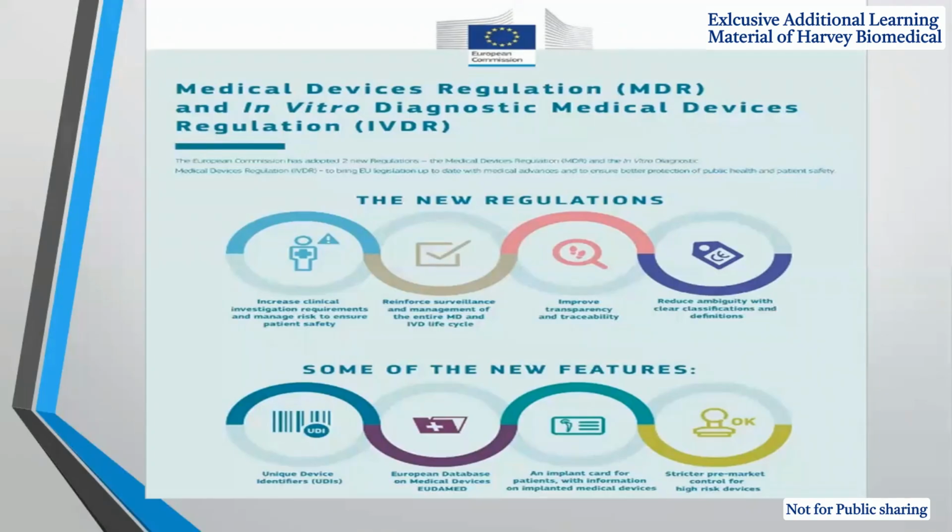And UDI is a very good feature. Why? Because based on this UDI, we can trace where our product is, and we can monitor our device identification with respect to the product identification. There are two types: DI and PI. Production identification is there, and the device identification also. In this barcode, the 2D barcode, we can identify all the DI and PI information. That is the labeling requirement. If you go into detail, then you will understand how it works.